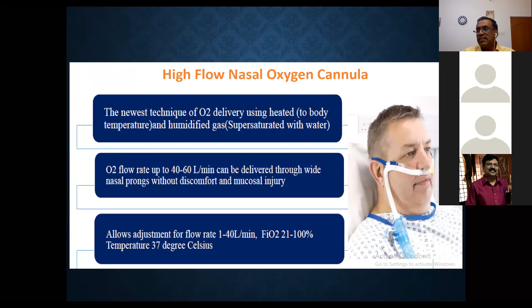But shortly, you can see it is the newest technique of oxygen delivery using heated and humidified gas. That is, the gas delivered to the patient is supersaturated, and an oxygen flow rate of 40 to 60 liters per minute can be delivered through wide bore nasal prongs without discomfort and mucosal injury, and it allows adjustments for flow rate of 1 to 40 liters per minute and FiO2 of 21 to 100%, and temperature of 37 degrees centigrade. It doesn't need any ICU setup. You can use this machine in the ward and the critical care ICU also for respiratory failure management.